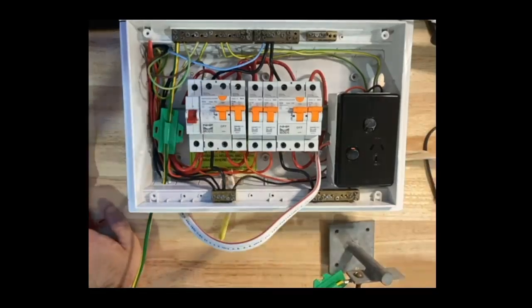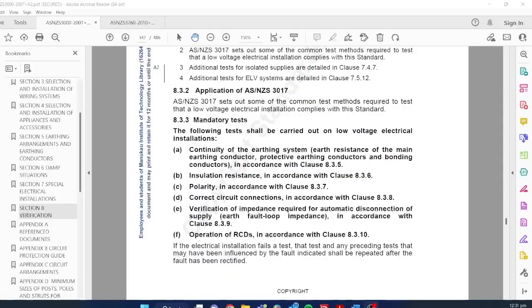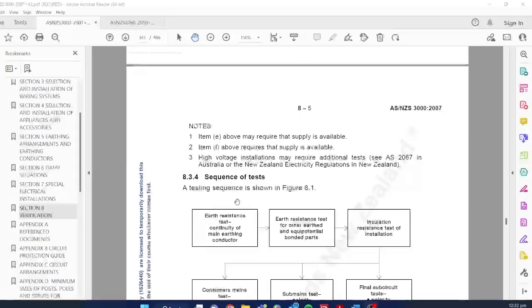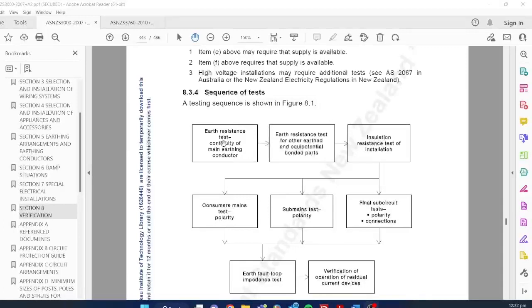Okay, so the next thing we will look at then is our standard AS/NZS 3000. And what does that say about our testing? Well, I'm going to go once again to section 8, because section 8 contains all of our testing. And if I scroll down to 8.3.3 here, you will see it tells us about some of the mandatory tests. And one of them is continuity of earthing system, earth resistance of the main earthing conductor, protective earthing conductors, and bonding conductors. So those are the three things that we just mentioned. If I scroll down a bit, we will see 8.3.4 tells us our sequence of testing. And we see there that earth resistance test, continuity of main earthing conductor, earth resistance test for other earth and equipotential bonding parts are our first two tests. So these are the first ones that I'm going to do when I'm commissioning a new installation, or when I'm testing a new installation before I commission it.